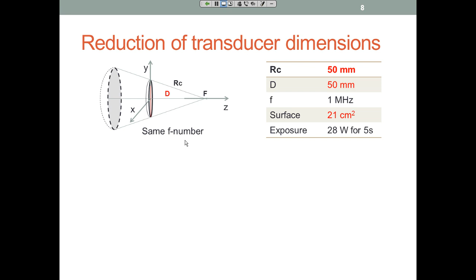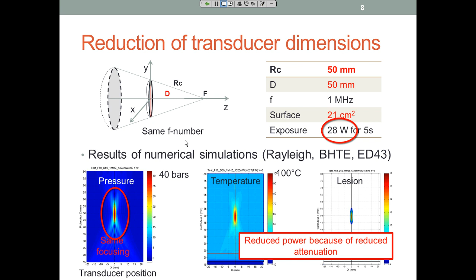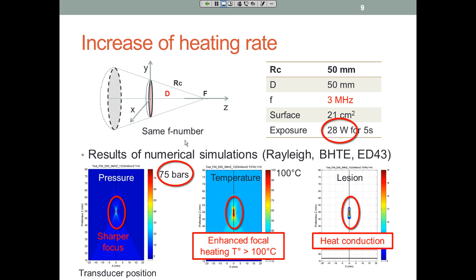So now the transducer is smaller, same frequency. And you can see we get the same focusing. The scale is a bit different, it's why it's larger, but it's the same. If you want to reach this 100 degrees Celsius at the focus, then you need only 25 watts per 5 seconds. And you can improve even more this strategy because you have reduced attenuation, so you can increase the frequency and still get very sharp focus with very efficient heating. So this is to say that it is very important to adjust the shape of the transducer according to the target. If you have a fat layer that prevents the tissue to be treated, then just go beyond it.